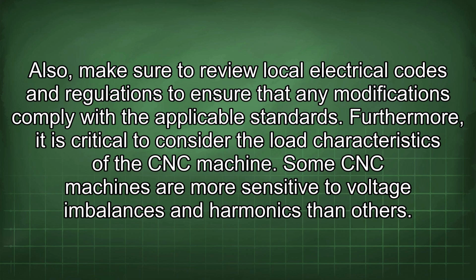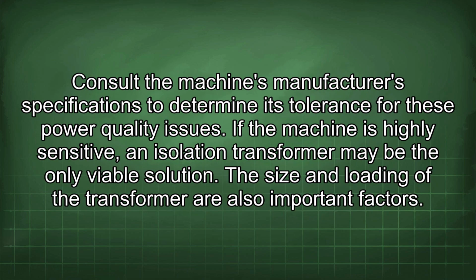Furthermore, it is critical to consider the load characteristics of the CNC machine. Some CNC machines are more sensitive to voltage imbalances and harmonics than others. Consult the machine manufacturer's specifications to determine its tolerance for these power quality issues. If the machine is highly sensitive, an isolation transformer may be the only viable solution.